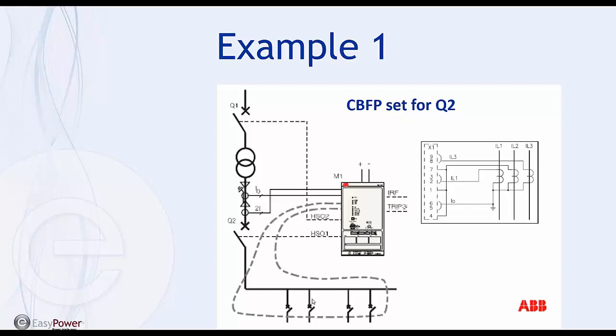So if you were to have an arcing fault in the zone of protection, once the current level, which is just a minimum value, is picked up, and you have light and current, then you would issue a trip from the high speed output. That's your 2.5 milliseconds, and then the breaker would trip. If the breaker did not trip, then you have that pre-programmed delay that results in high speed output 2 tripping Q1. So let's see how we set the dip switches here.